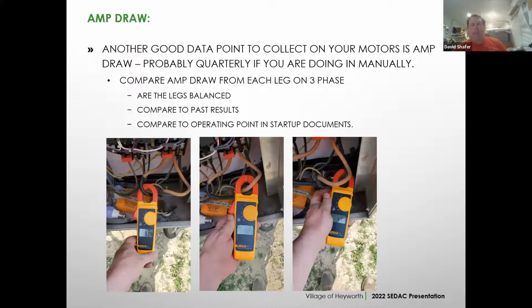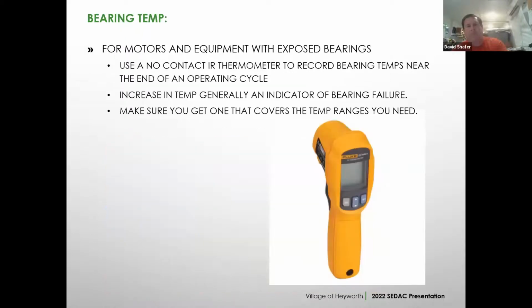Another good data point to collect from your motors is your amp draw. It's probably something you do quarterly if you're doing it manually. You want to compare the amp draw on each leg of your 3-phase motor. Are you balanced? How does that compare to past results? How does that compare to your operating point in your startup documents or the manufacturer's documentation? In this case, you can see I'm pulling between 31 and 33 amps. That motor was only supposed to be pulling, I think, around 22 amps at the current loading. So obviously we've got an issue that needs to be addressed.